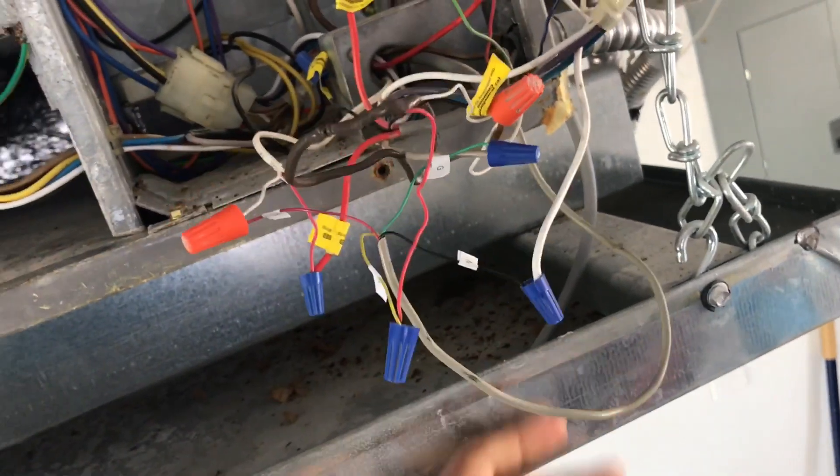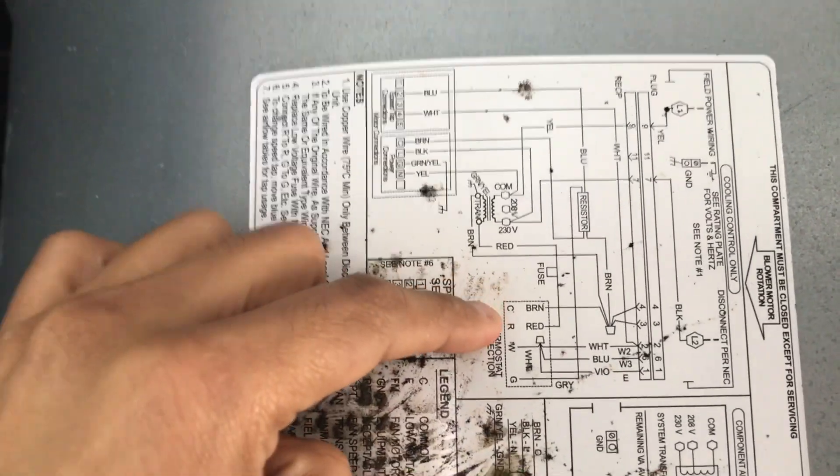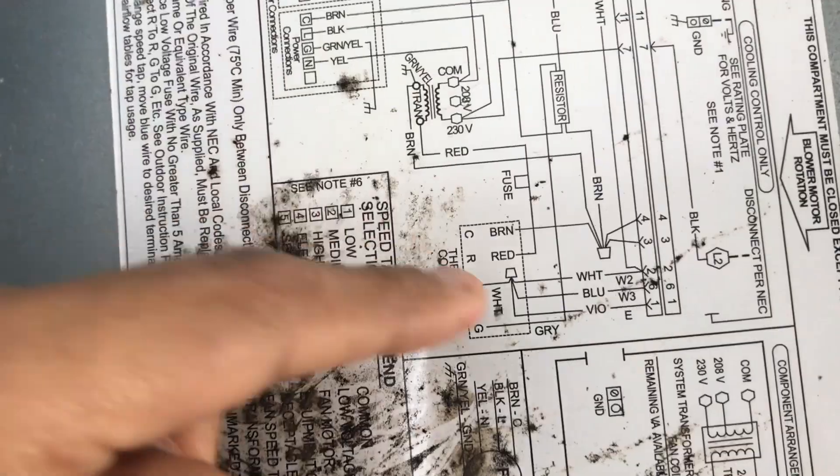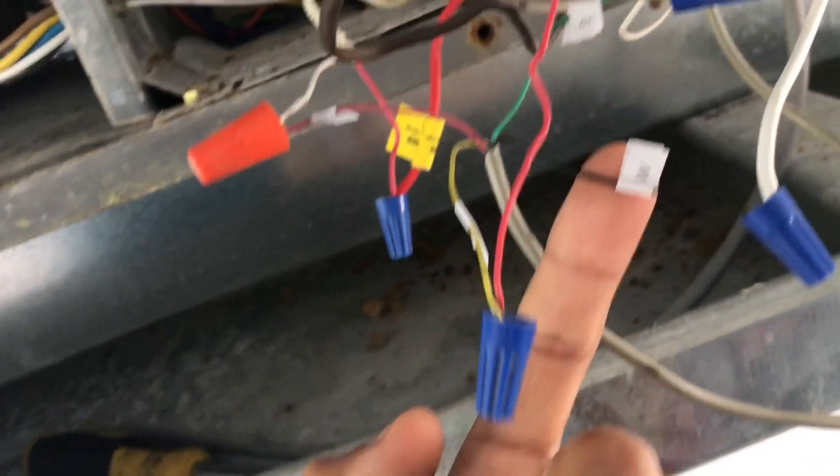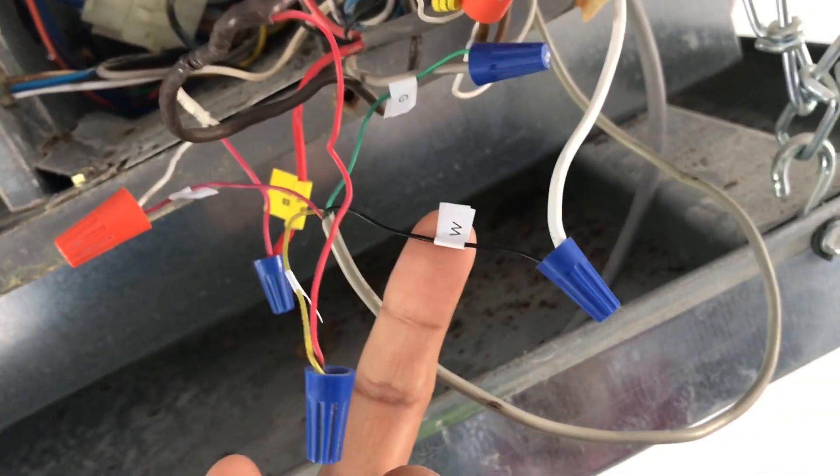Locate the schematic. In this case we have the C wire which is brown, which is right here. Then we have the red, which is red. White goes to a bundle of wires: white, blue, and violet, which is this bundle right here. It's connected to the white cable that's coming from the thermostat.